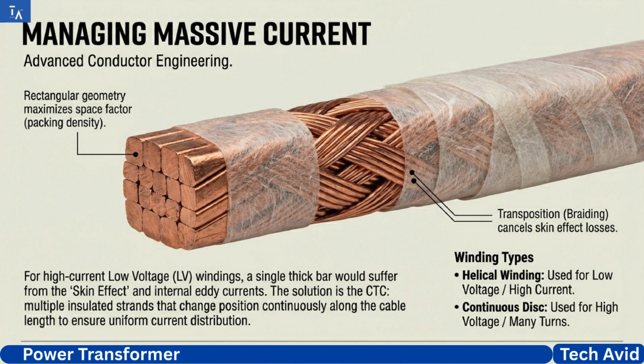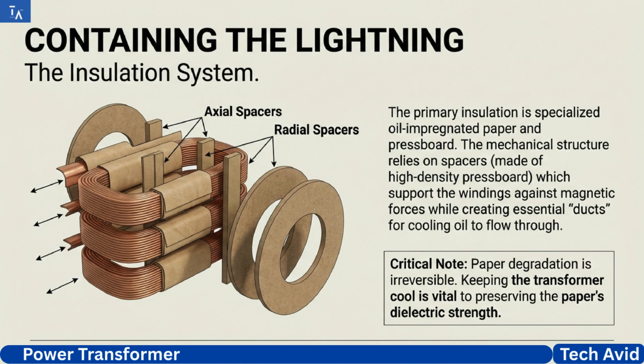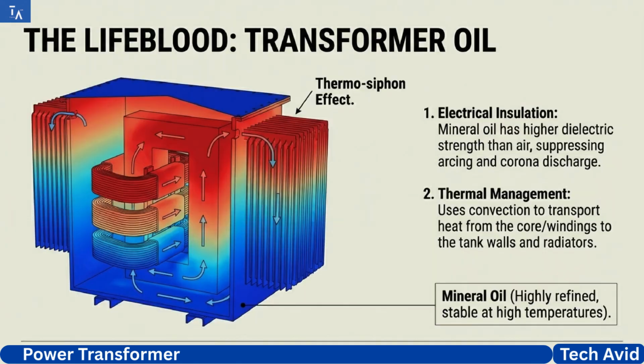We're now dealing with hundreds of thousands of volts. The battlefield is the insulation system. The primary insulation isn't plastic or ceramic. It's specialized oil-impregnated paper and pressboard. Spacers made of this pressboard do double duty. They physically support the windings against tremendous magnetic forces, and they create channels or ducts for the real hero, the cooling oil.